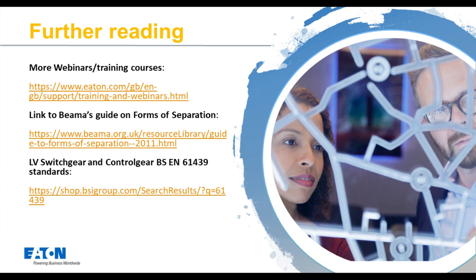Okay, and there's another question here regarding safety. Is there any difference between a group-mounted or a compartmentalised way of forms of separation? Yeah, although both means are acceptable, when it comes to a group-mounted solution, there's always that risk that if a breaker sees a fault and clears the fault, it generally releases ionised gases within an enclosure, and that can have an effect on adjacent circuits. So when you've got a compartmentalised solution, you reduce that risk because the gases are contained within the compartment. Okay, cheers.